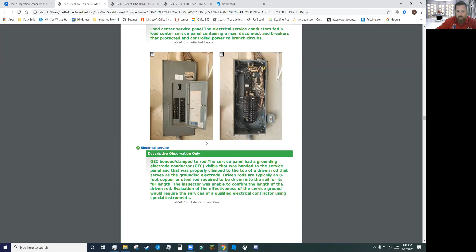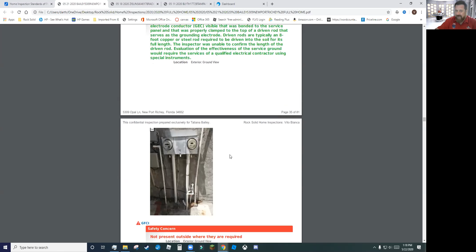Here's the electrical service - there was no service mast or drip loop to look at, so really I'm looking at the meter. I want to make sure the lockout tagout is in place. Looking down here where the grounding rod is, I want to make sure the GEC, the grounding electrode conductor, is clamped to the rod, and the rod is driven into the ground. If it's not visible, I'll note that it's not visible - it's not a defect, I'm just letting them know I couldn't physically see it.